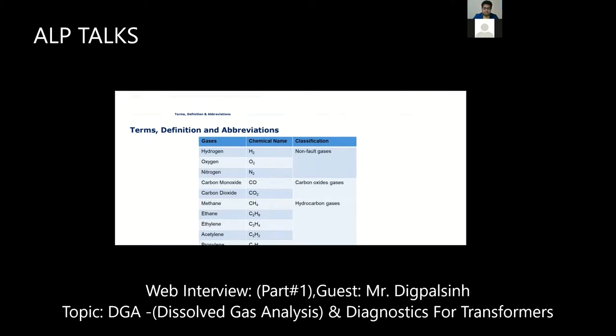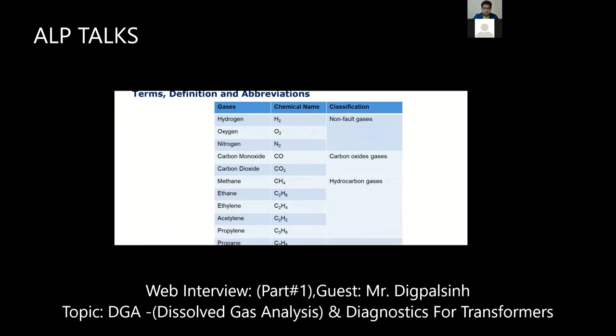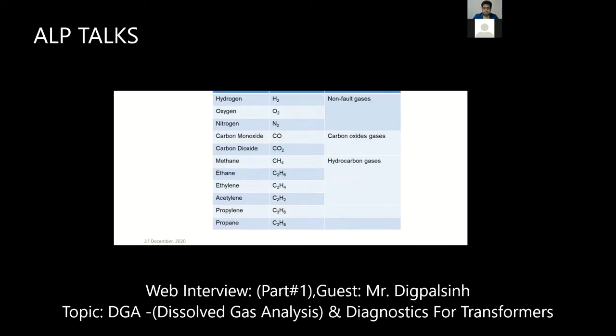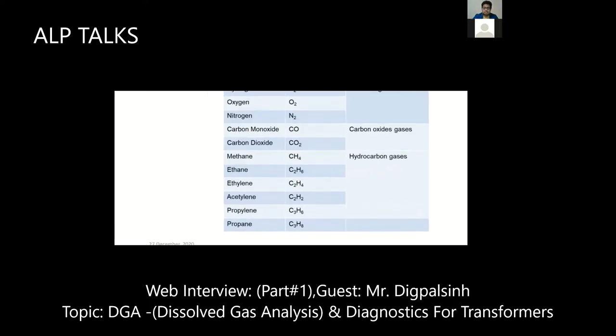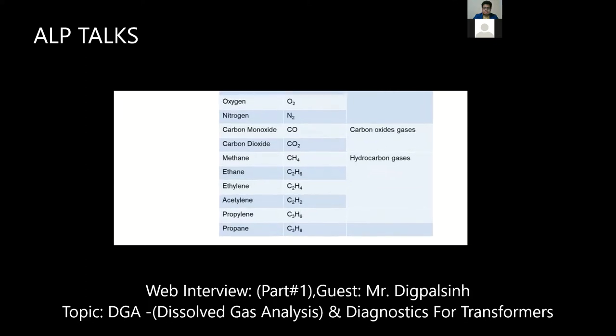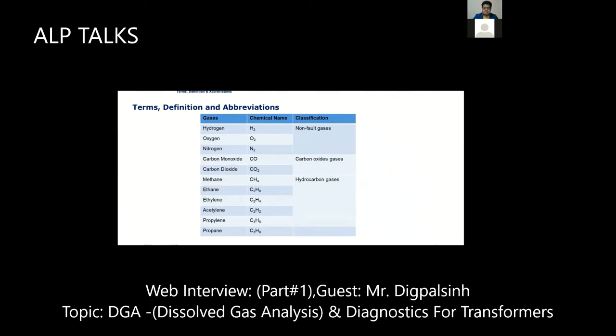Then we come to the carbon oxide gases, CO and CO2, carbon monoxide and carbon dioxide, which are directly connected with your paper insulation. When paper insulation decomposes, CO and CO2 will be generated. And then the final and major gases are the hydrocarbon gases, HC gases: methane, CH4, ethane, ethylene, acetylene, and propylene and propane, which we need not discuss at this stage. So in today's discussion, we mainly discuss from carbon monoxide to acetylene, and hydrogen.